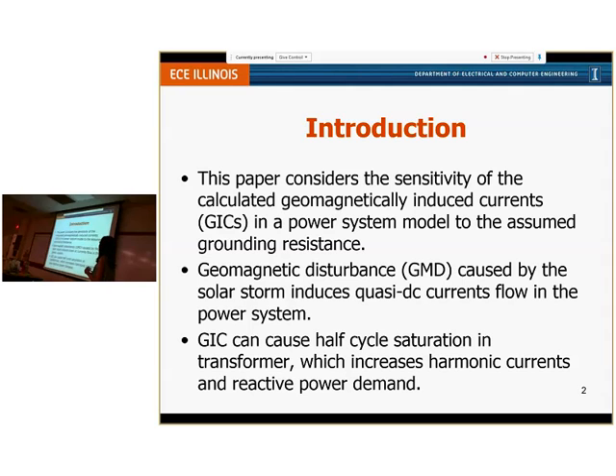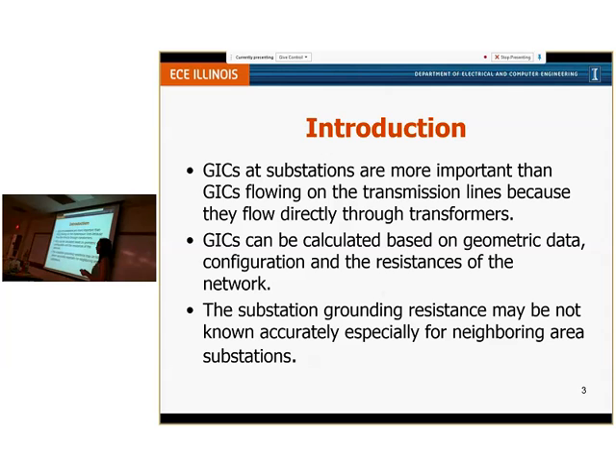In short, it's GIC. And GIC can cause half-cycle saturation in transformers, which increases the harmonic currents and also the reactive power demand. The earthing GICs, which are the GIC flowing to the substation, are more important to us than the GIC flowing in the transmission line because they flow directly through the transformer. And if their magnitude is too high, they can saturate the transformer, which we don't want. GIC can be calculated based on geographic data, meaning the latitude and longitude of substations, the configuration, and the values of the resistances in the network.